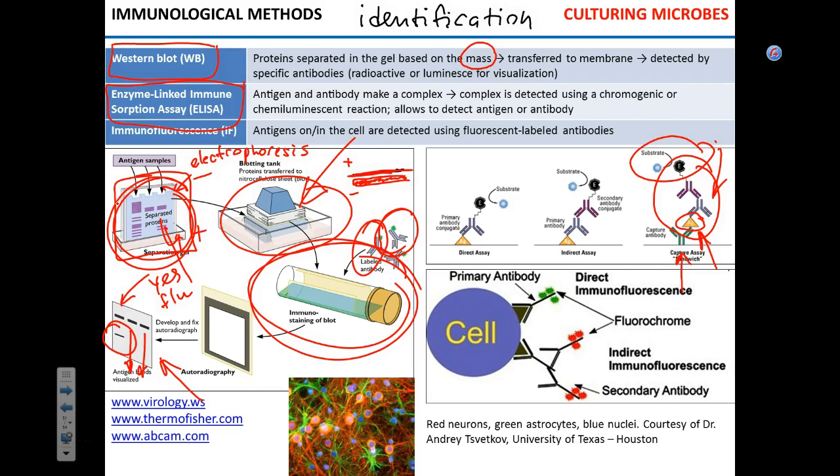That's not for manual. That's for machines. This is another advantage of ELISA. It is very easy to make automatic. To the point when you have all your samples lined up in the tray. That makes sense? You load the tray in the machine. The machine already has all the antibodies. It has a plate. It has all the buffers used to wash the plates. Everything is there. So you load the tray and you push the button. The machine will load the samples, will incubate them, will shake them, will wash them, everything will be done.